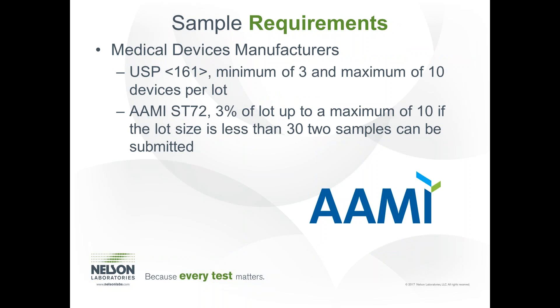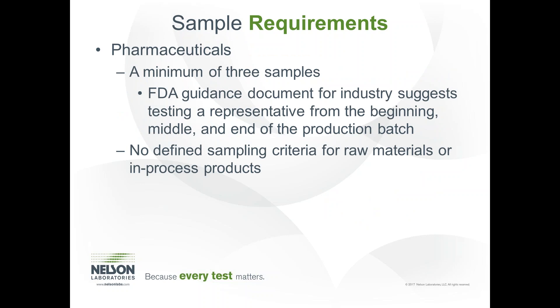Regarding sampling requirements, according to USP 161, you should test a minimum of three and a maximum of 10 devices. AAMI ST72 suggests 3% of the lot up to a maximum of 10, and if your lot size is less than 30, two samples can be submitted. For pharmaceutical products, FDA requires a minimum of three samples be tested, and they recommend testing samples from the beginning, middle, and end of the production batch. There is no defined sampling criteria for raw materials or in-process products. With medical devices, we typically test devices pooled, so it is an average of the 3 to 10 devices, whereas pharmaceutical products are typically tested individually.